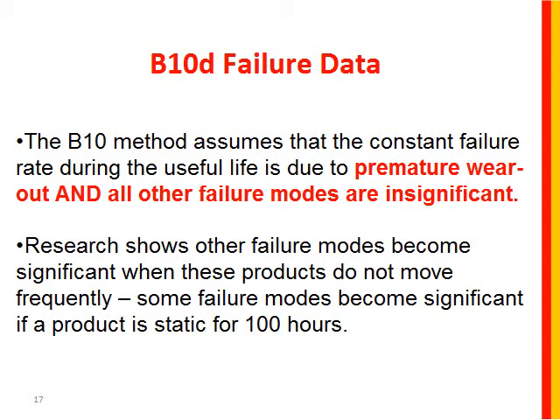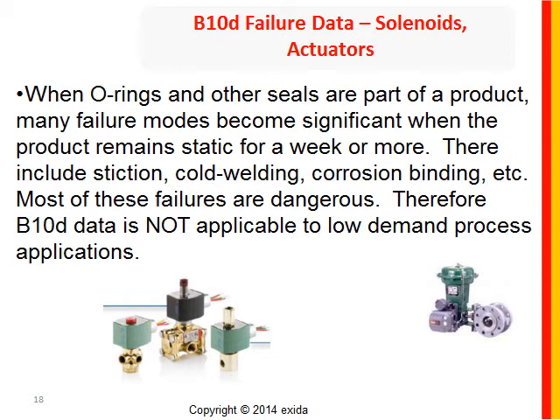Why do I say that? When O-rings and other seals are part of a product — like in a solenoid valve, actuator, ball valve, or most types of products used in the process industries — there are other failure modes, including stick-slip, cold welding, corrosion binding, and even metal-to-metal binding when moisture is present. Most of these failures prevent the product from performing its safety function and therefore are dangerous. You've got to be extremely careful about looking at the source of data. If a data source has any derivation based on mechanically dynamic applications, it should not be used in low demand. Often, when a certification agency uses such a method, they will post a warning on the certificate, stating they've assumed at least 10 demands per year — meaning do not use this information for process industries.